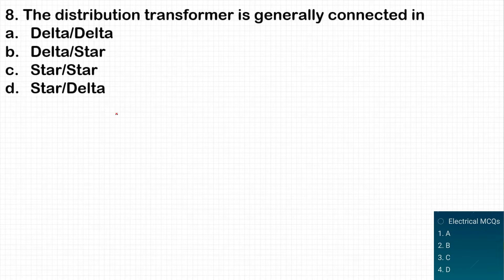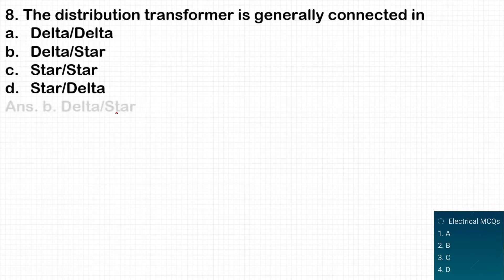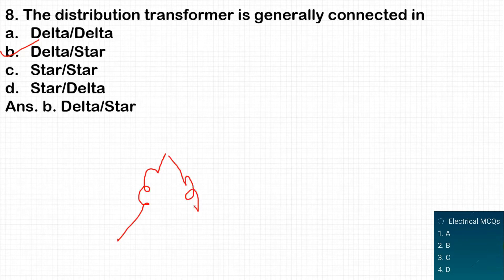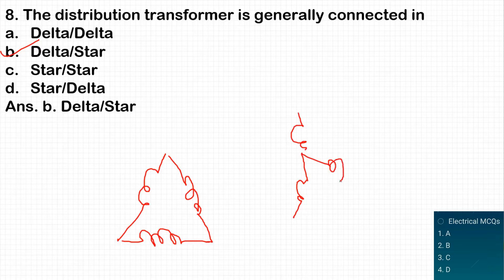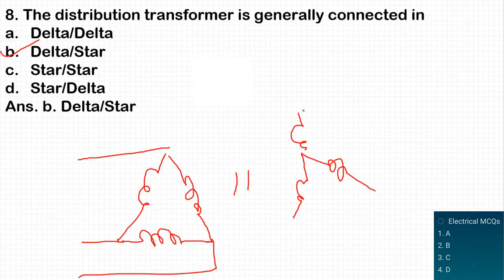The next question: a distribution transformer is generally connected in which form — delta-delta, delta-star, star-star, or star-delta? It is always connected in delta-star. As shown here, the primary is in delta and the secondary is in star. Due to the star connection on the secondary, the neutral point is easily available, allowing single-phase loads to be easily connected.